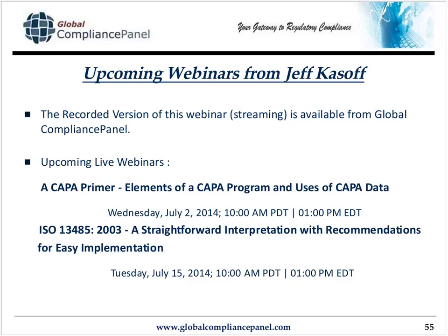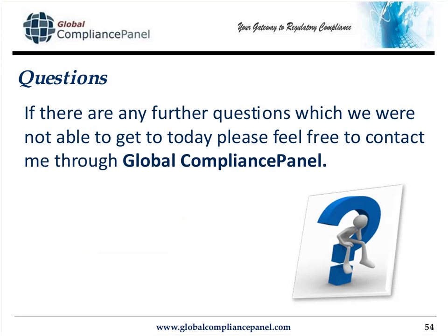Okay, I have another question. The question reads, when is clinical data required? Interesting question. Clinical data is only required when you feel that you're unable to, by bench testing, provide data of safety and efficacy. So with regard to safety, you can perform biocompatibility testing in most cases on your device. And when it comes to efficacy, if your bench testing, if your in vitro testing, if you will, is insufficient, you will need to perform clinical testing. So I hope that clears that up.